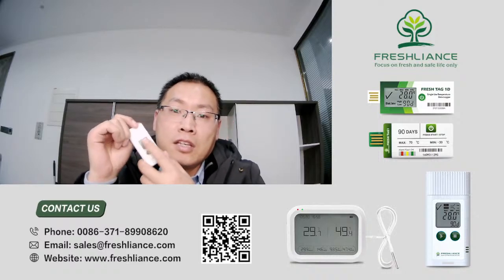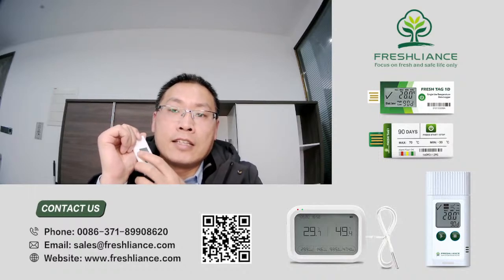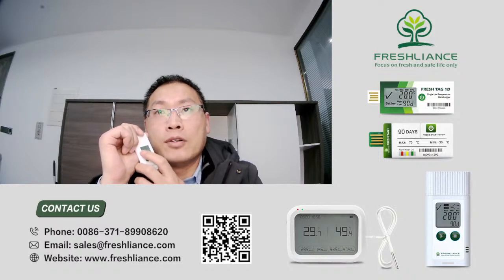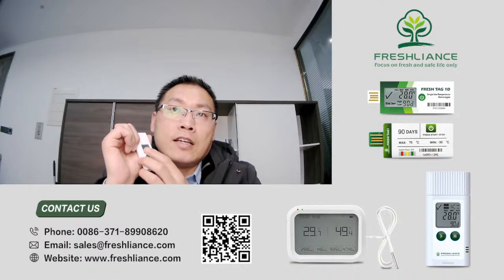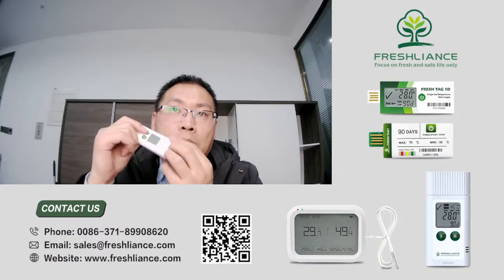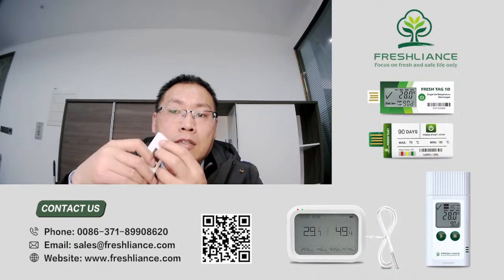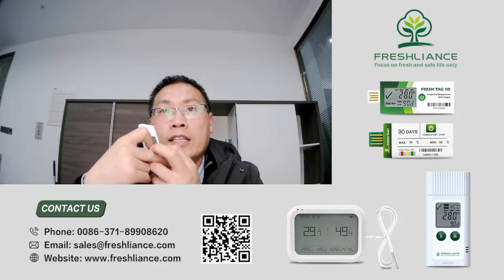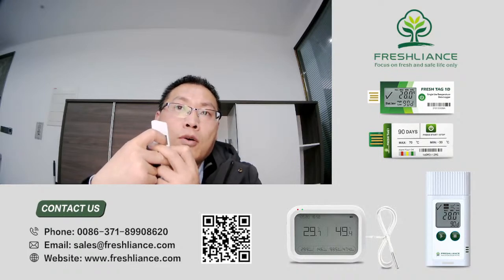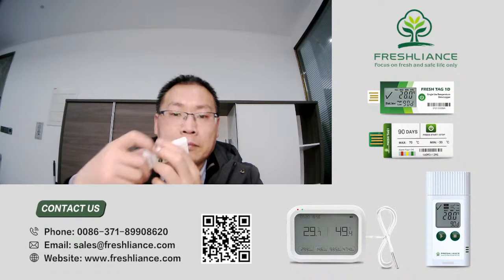Now we talk about the start modes. The third start model is the time started. Through the time started mode, you can set a preset start time, such as 10 minutes or 30 minutes. Then when you pull it out from the computer and press the button, it will not make a recording immediately. Just after the 10 minutes or 30 minutes you preset in the software, it will start to make recording.